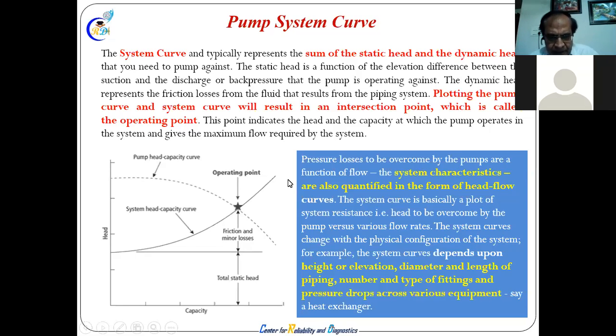Please mute yourself. System head capacity curve. This system head capacity curve would start from 0 if there is no static head. Meaning the water is here and our pump is right next to the water. System head 0, static head 0, right? If you take the fluid pump, water, near to that. So if there is height, then static head comes into the picture, and these are the dynamic losses. That's why you get the system curve.